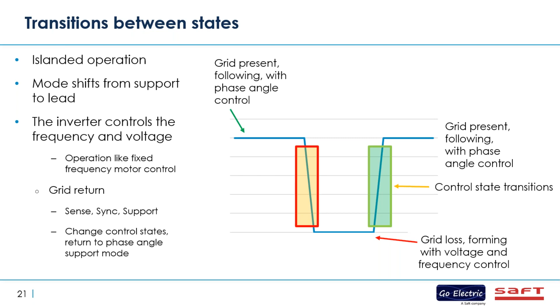When the grid returns, we sense it, we sync to it, and then we go back into a support mode. We change the control states and return to phase angle support mode. So the graph on the right, the grid's present, we're following with phase angle control. We sense a grid loss, we go into islanded operation. When we're in islanded operation, we're forming the system with voltage and frequency control, so we become the prime. When the grid returns, we do another control state transition back into phase angle control with current support and kVAR support for the larger grid.